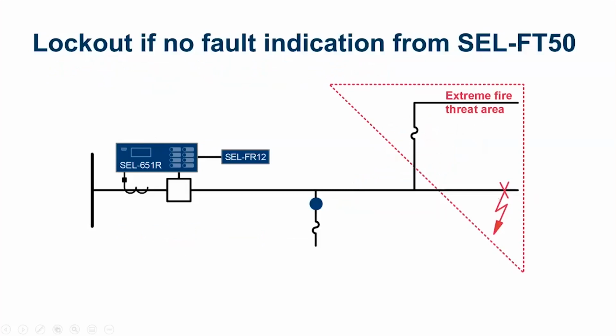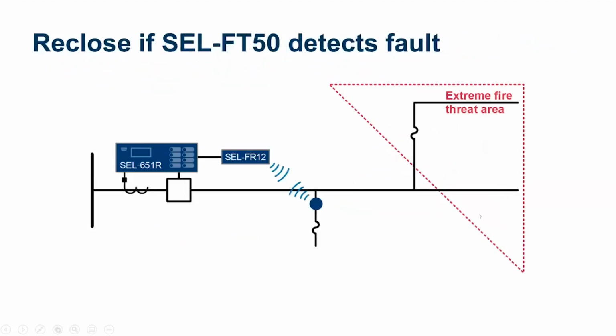But if the fault is not in the extreme fire threat area, rather if the fault is on the lateral where my important loads are, then I'm going to send this signal, because this is going to detect the fault on this lateral. And the FR12 will know that, okay, the fault is on this lateral, which is a critical load, you should reclose. So block reclose on this one, allow reclose on this one. So this is what the dynamic control looks like.